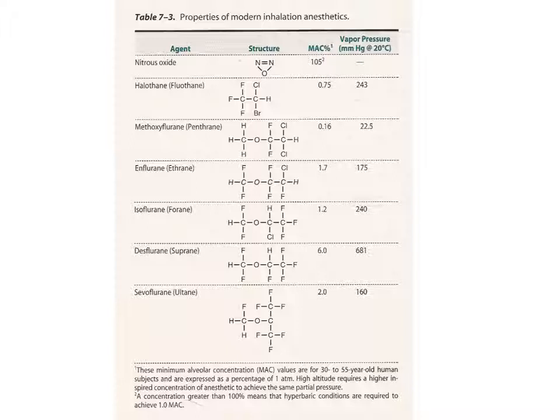And then the opposite end has a little device that slides into the vaporizer to fill it, and they are shaped differently. So you shouldn't be able to take a sevoflurane vaporizer filler and connect it to a desflurane vaporizer or an isoflurane vaporizer because it won't fit. Whereas in the past, you just unscrewed it and poured it in, and you were good to go. So vapor pressures were important, and you need to know the numbers. You can't really do it anymore, but it's just historical.